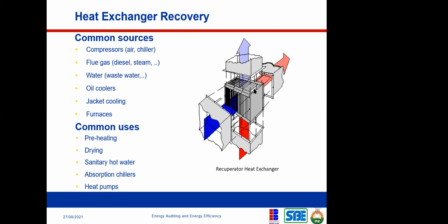If you look at what's going on here, this is exhaust gas that is going out, the red one, going out from the burner, from the boiler. Now this is air that is coming in. This blue color is the air, and it's cold. It comes into this heat exchanger, makes contact with the hot exhaust gas, and comes out warm. So the hot exhaust gas now comes out cooler. It's no longer as hot as it was because part of the heat has been stripped off. So it comes out colder, right? And it goes into the environment. If we did not do this, the whole of this heat would have been lost to the environment, which is not good. So, heat exchange recovery, common sources: compressor.